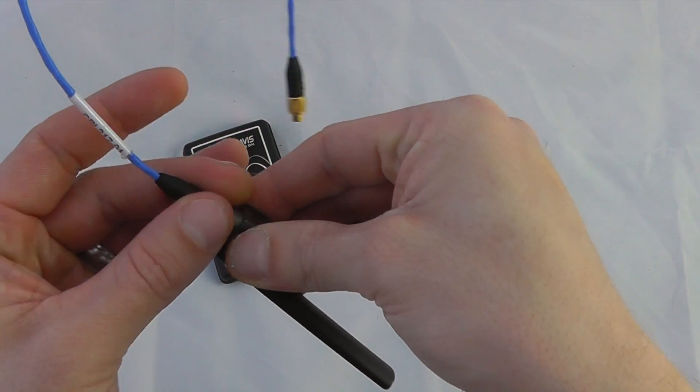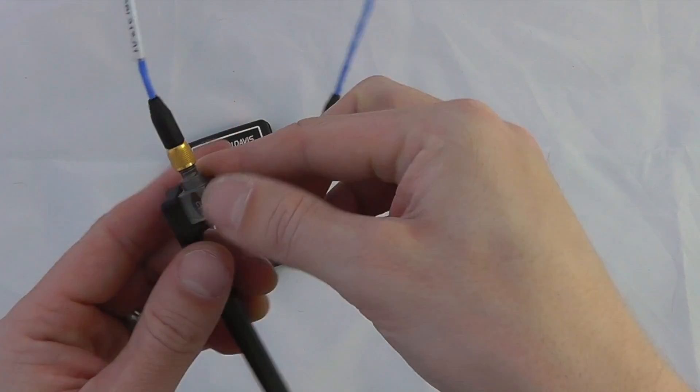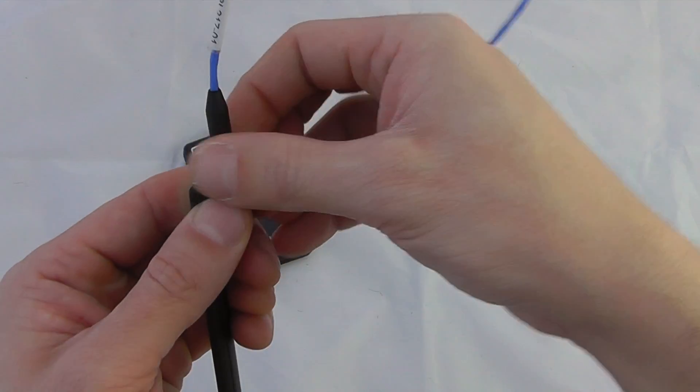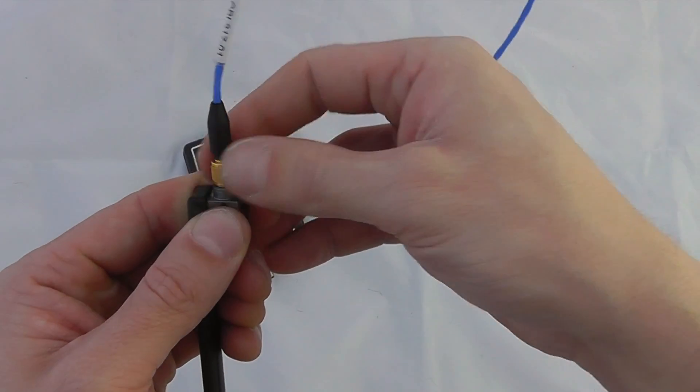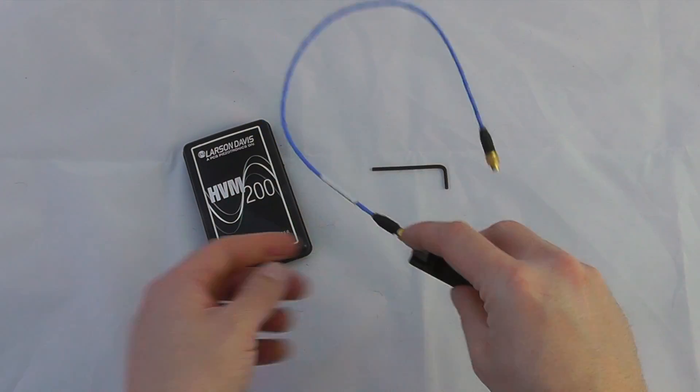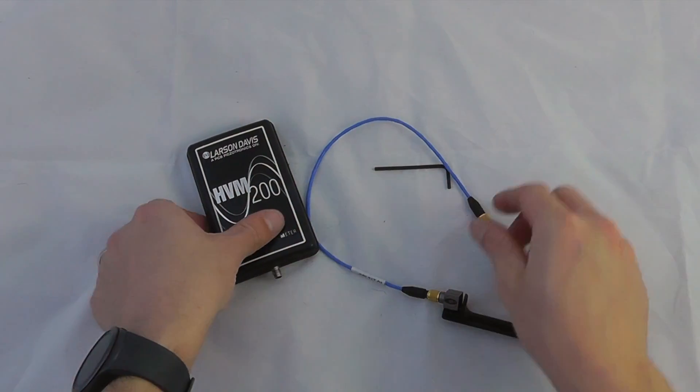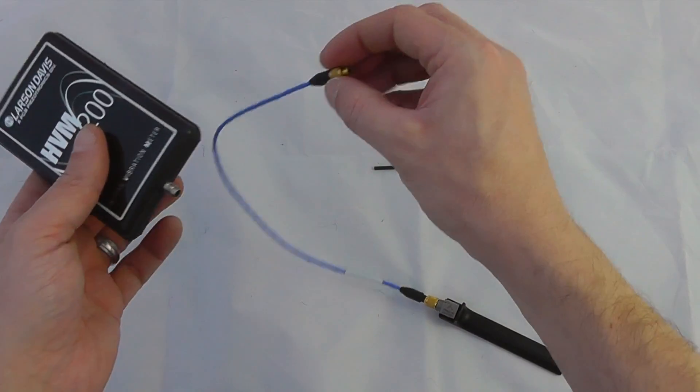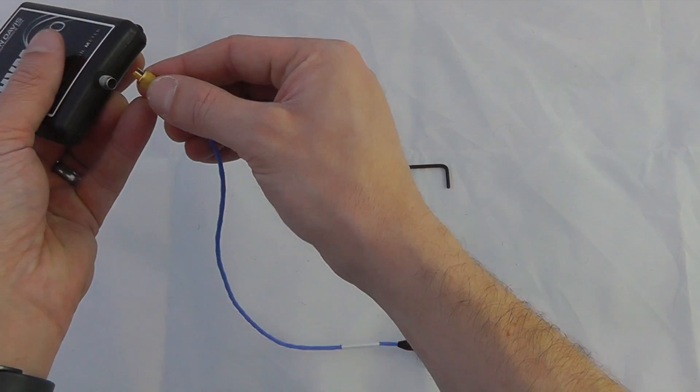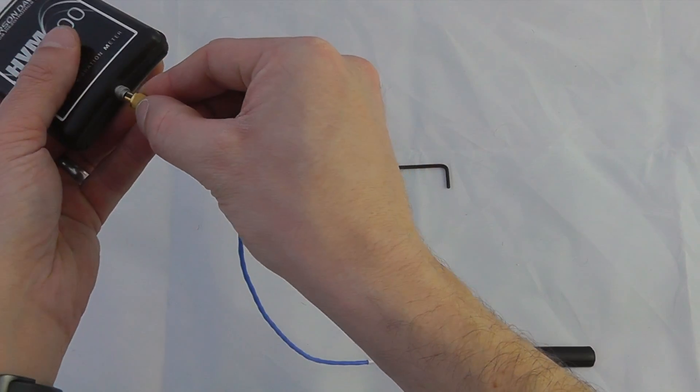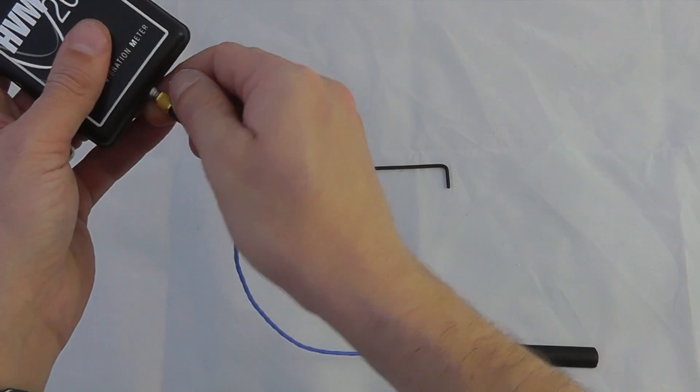Push it into position and then screw into position on the accelerometer. It is important you get finger tightness on here. Not too tight or else we'll never be able to remove it from the accelerometer, but finger tightness. And then there is a similar technique for attaching to the unit itself.